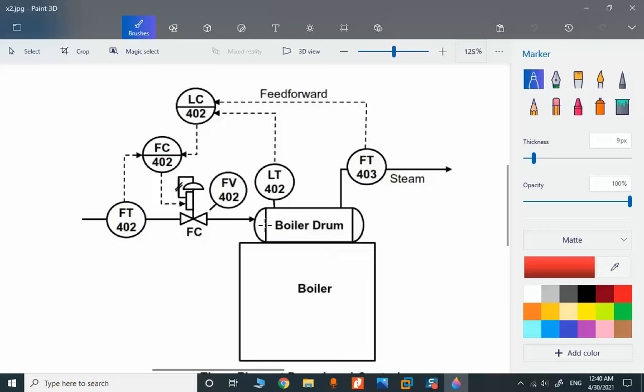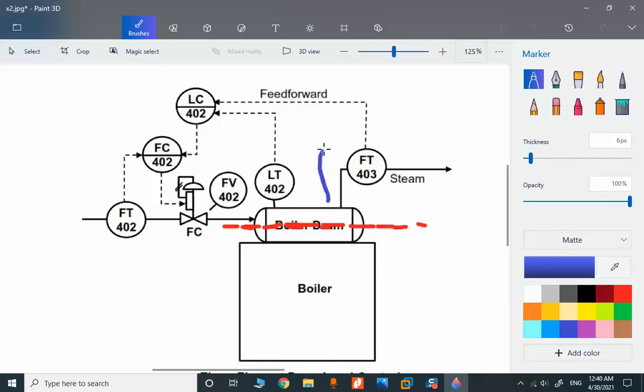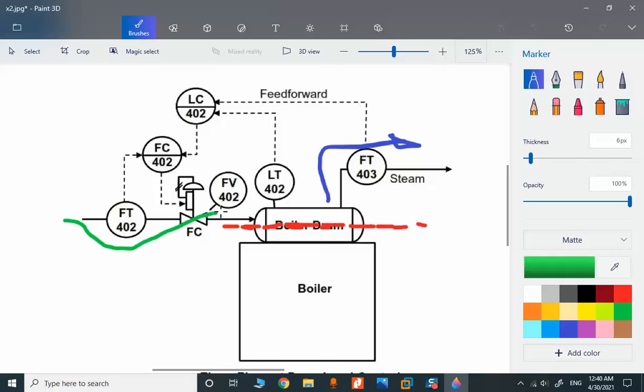The boiler level is controlled by amount of steam, steam demand, the amount of steam that is exported. Steam flow is an indication of the amount of steam exported and we need to support the steam drum with proper fresh water via this flow control.